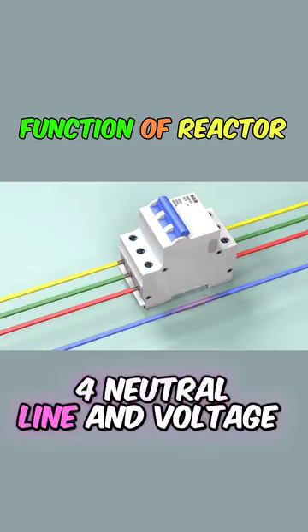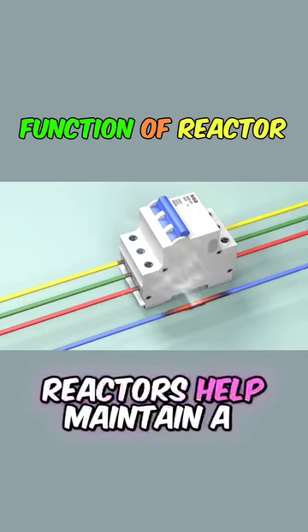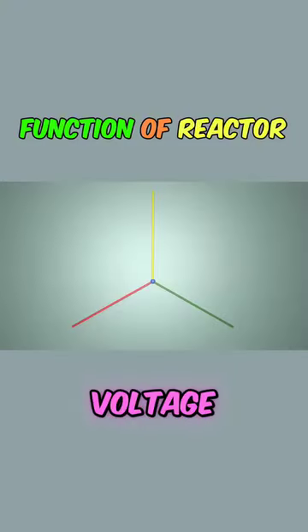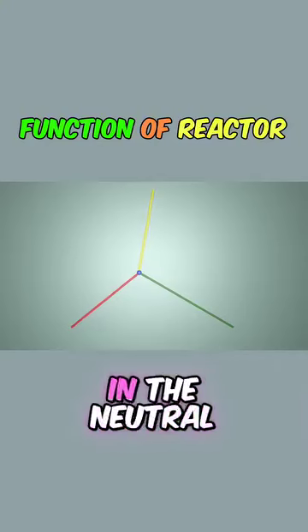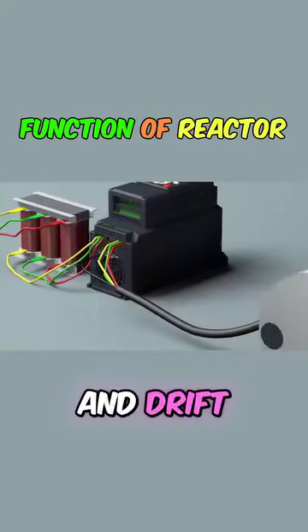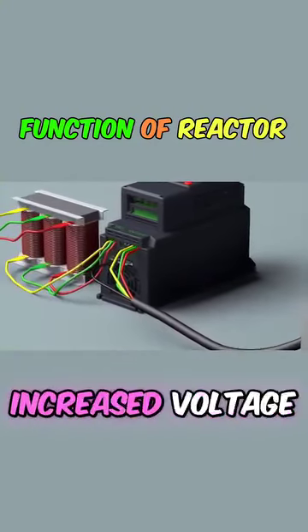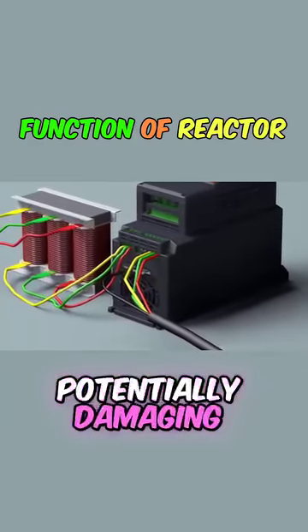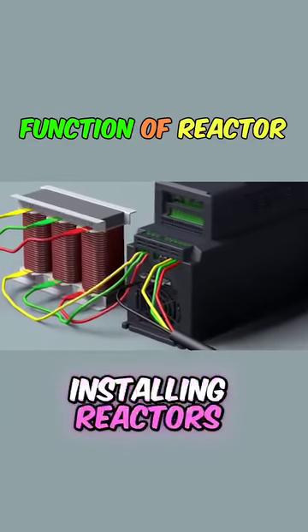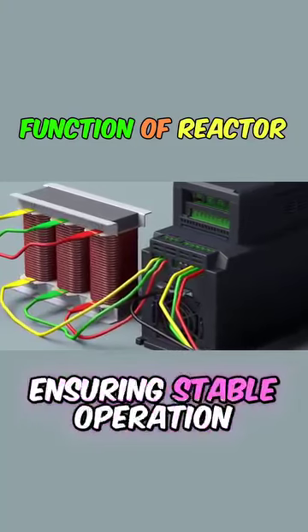4. Neutral line and voltage balance. Reactors help maintain a balanced three-phase voltage. Without them, excessive current in the neutral line can cause it to burn and drift. Low-power items may experience increased voltage, potentially damaging electrical equipment. Installing reactors mitigates these issues, ensuring stable operation.